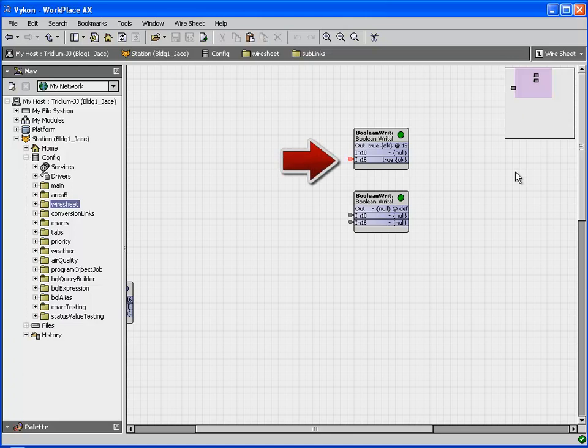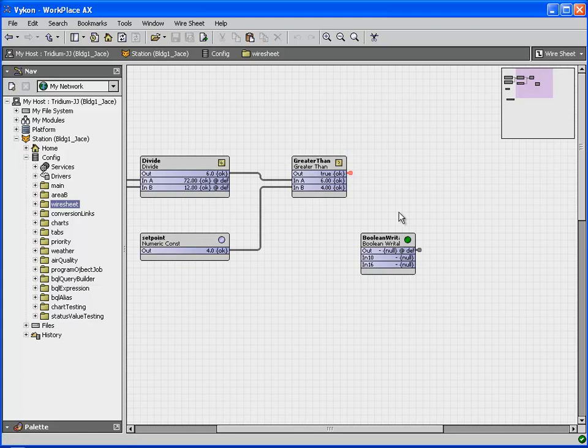The hyperlink is also designed to sort of center itself on the link and to highlight the stub for us. So that's going to facilitate identifying that link, particularly if we have a busy Wiresheet or a large Wiresheet. Instead of having to manually position and navigate ourselves and find that component, it's now centralizing on that and highlighting it for us. So this is a huge time saver when trying to follow off-page links between your control logic.